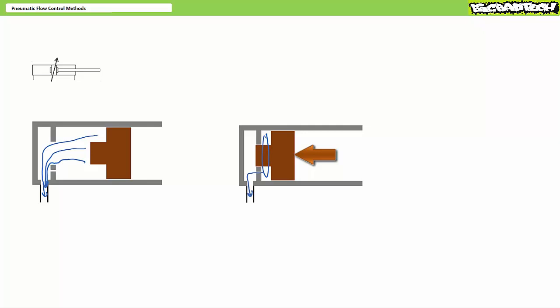If the cushion is adjustable, a technician can increase or decrease the size of this restriction so that the cushion of air is exhausted quickly or slowly, thus saving the piston face from repeated and forceful impacts at the limits of extension and retraction.